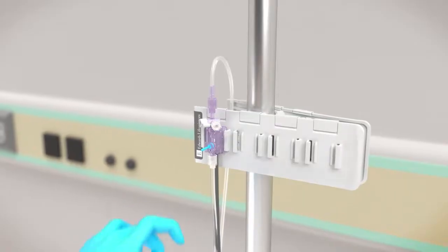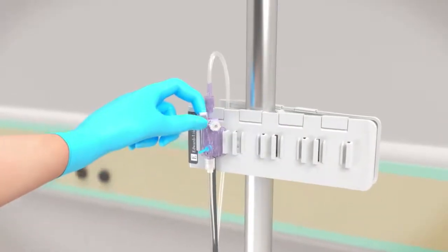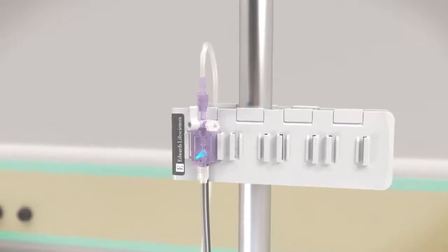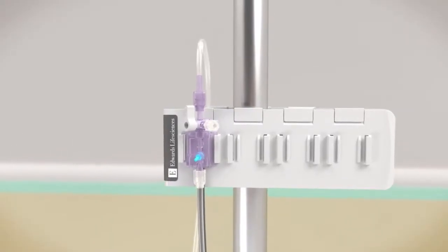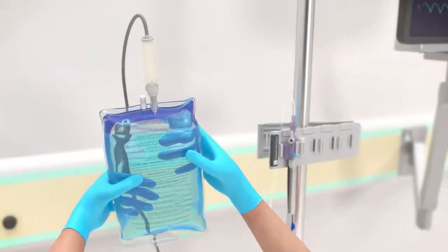Open the vent port by turning the stopcock toward the patient's pressure tubing and away from the transducer while leaving the vented cap in place.